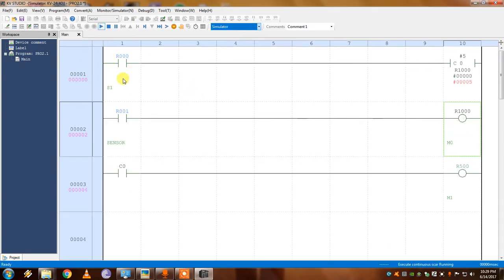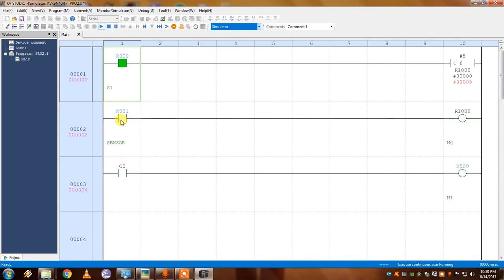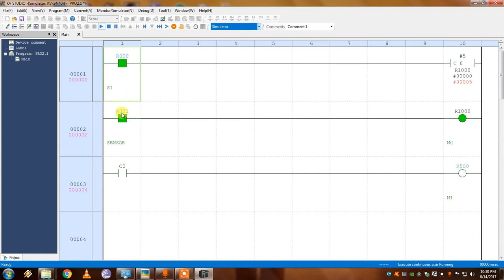In simulation mode with the running condition active, the input is on so the counter is enabled. Each time the sensor gives a pulse to memory M0, the counter increments: one, two, three, four, five. After five counts, the counter is enabled and gives the connection to the motor. This is how the counter works. Repeating the test: one, two, three, four, five — the motor activates again.